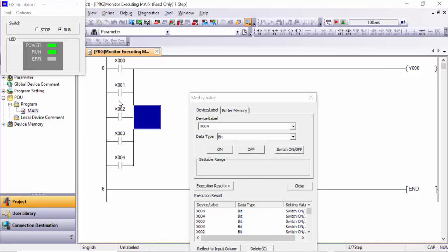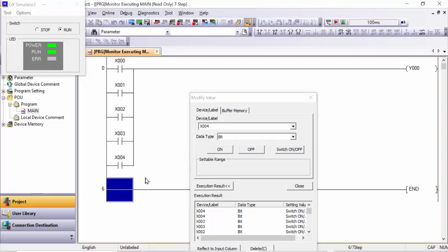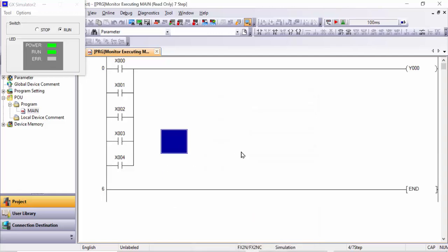So this OR logic we can create in the PLC. This way, however many internal or external bits, for example signals coming from the field at NO or NC, and you say this signal on, or this signal on, or this signal on, whichever signals you would like to make OR logic, after that you can design this in the program, and I hope you understand this OR logic, how we can create it and how it performs in Mitsubishi PLC.